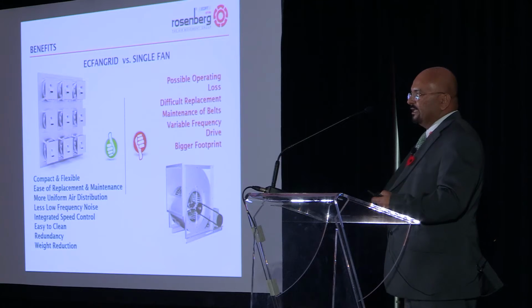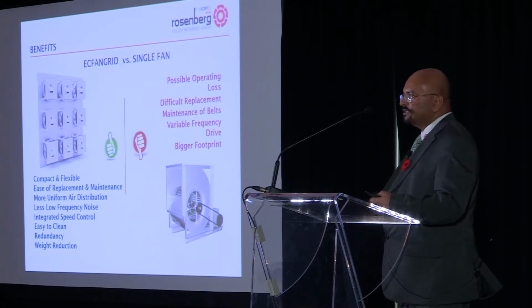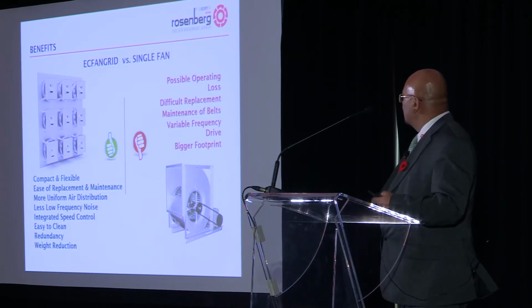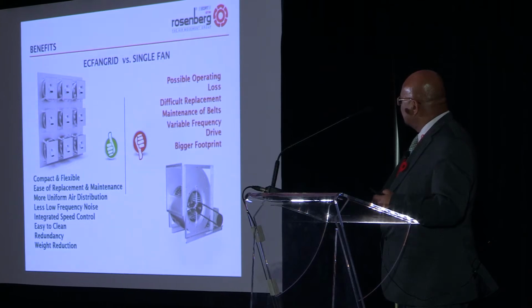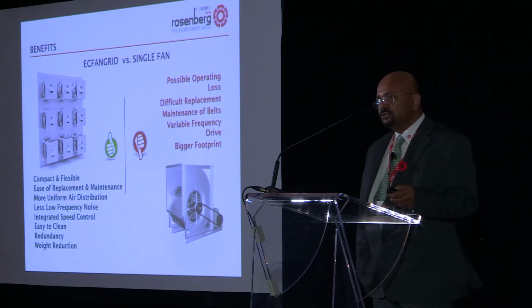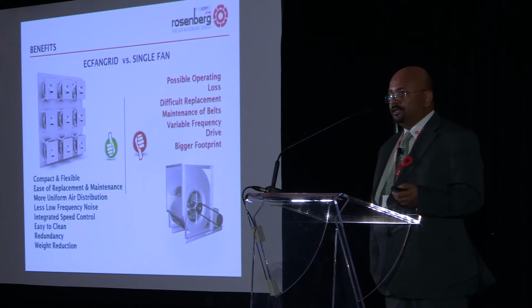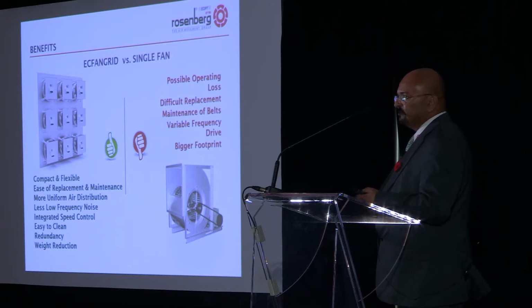So when we look at the existing fans, which are the belt-driven fans, how does the EC retrofit benefit over those older technologies? If you can see, the fan grid is very compact and flexible, easy to replace and maintain, with more uniform distribution across the fan grid. It produces less low-frequency noise, has integrated speed control, and is very easy to clean. It has redundancy because there are a number of fans, and very little weight. Compared to what you get from the single fan: operating losses, difficult replacements, you have to change the belts, you have to use VFDs with these, and it takes a lot of space.